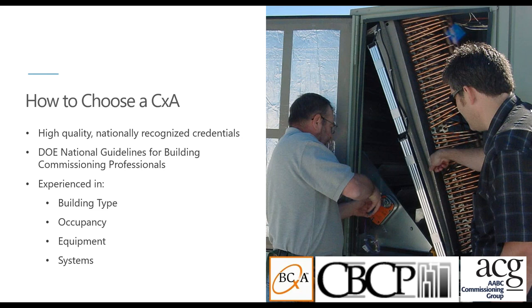So what's most important comes down to experience and ensuring that you're choosing someone who's got experience in the building type that you're working on, as well as the equipment that you're working on. There are no doubt many commissioning authorities out there who might be experts in hospitals, but may not be able to apply that same expertise to a lab building instead. Or maybe experts in air handling units with VAV boxes, but not experts in radiant flooring. So ensuring that they are familiar not only in the type of building, but in the type of equipment that's being used is of utmost importance in ensuring that you get the most quality, value-added benefits from a commissioning process as you can.